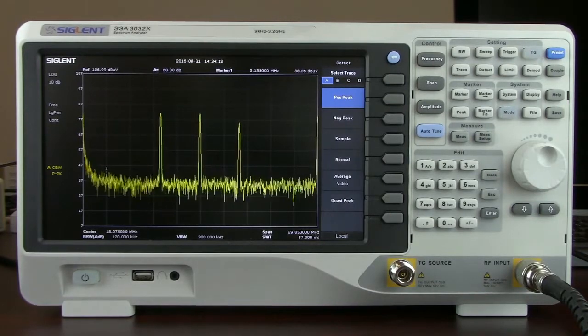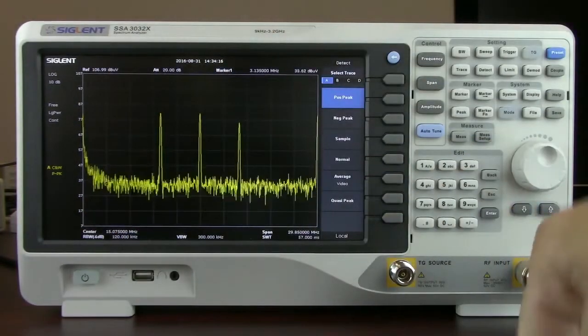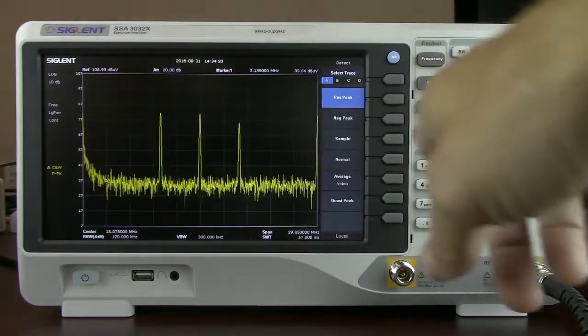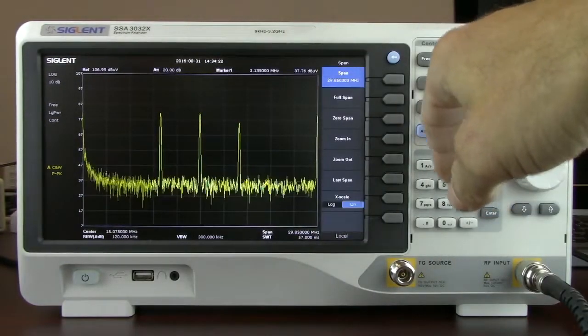Some other helpful features here with the SSA when it comes to performing pre-compliance measurements. Normally we have log amplitude and linear frequency. But in pre-compliance applications or compliance applications, we typically see log log. If we press the span key, we'll see that the X scale can be changed to log. So now we've got log amplitude as well as log frequency.